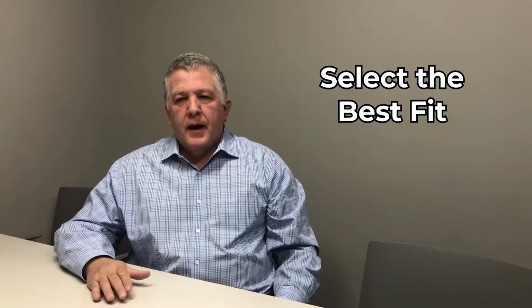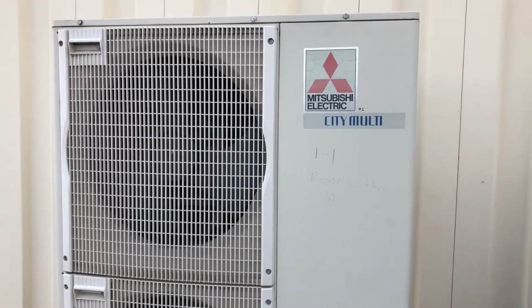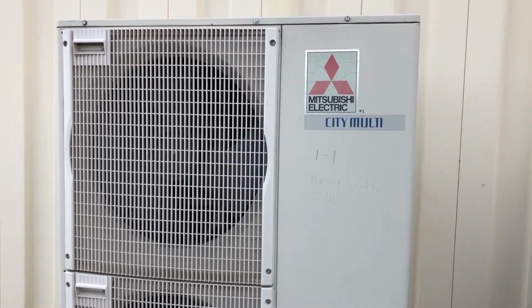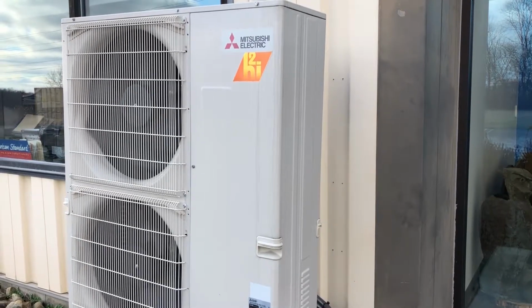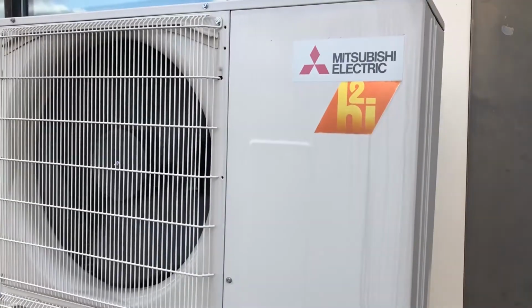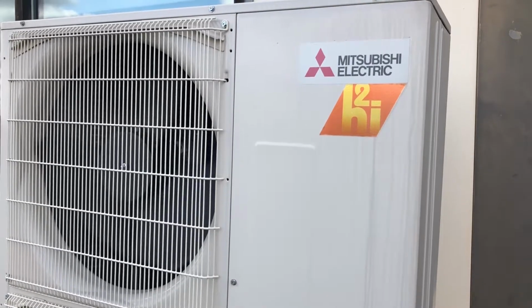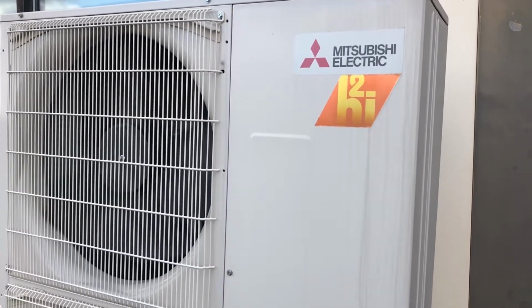Practically all VRF systems in the US are heat pumps, so it's just a matter of selecting which is the best fit between all heat, all cool, and heat recovery. One thing to keep in mind is just because a VRF system may have multiple terminal units doesn't mean you have mode control at each indoor unit. The most important thing to remember with the all heat, all cool systems is that all terminal units need to be in the same mode at the same time. In other words, there's no real auto changeover in these type of systems.